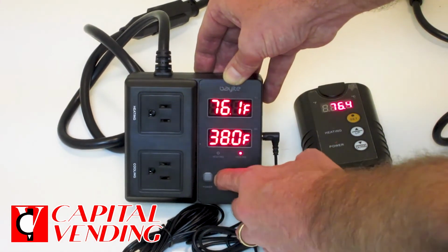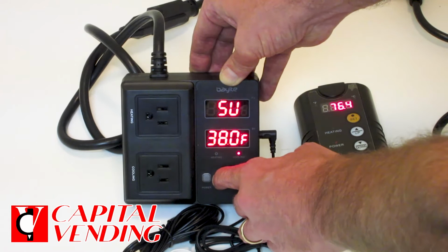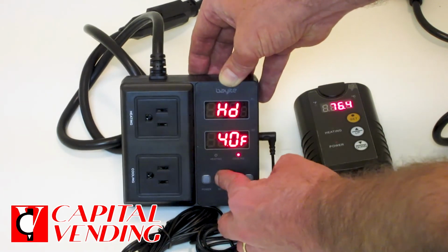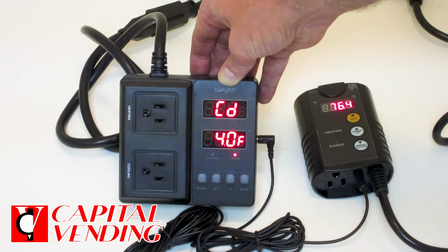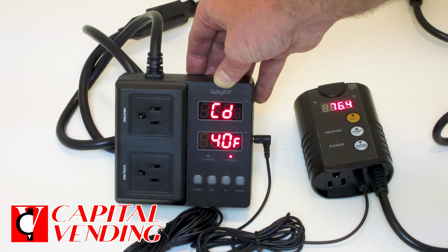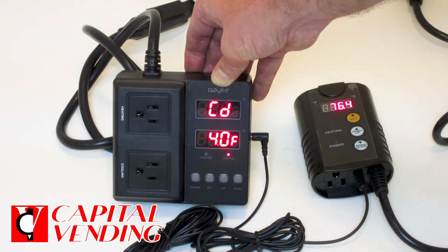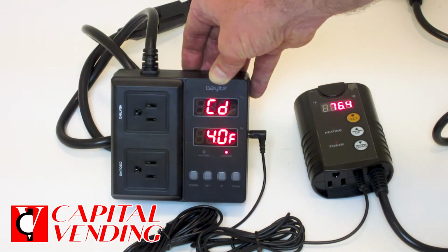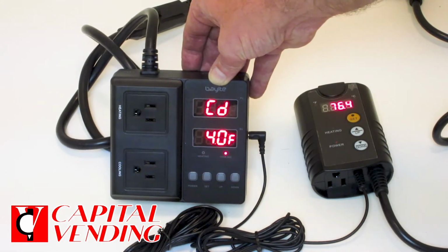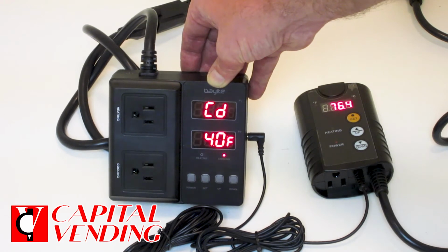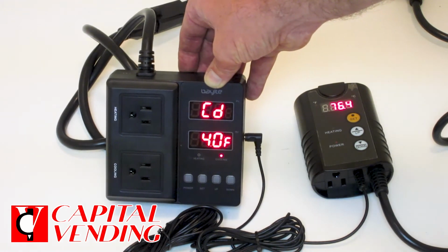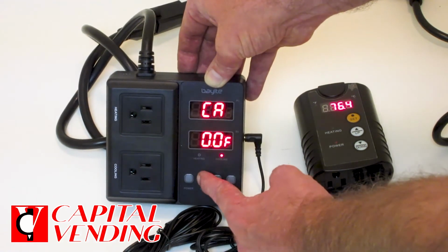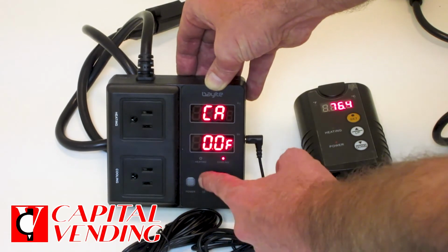So now I'm going to press and hold my set button again for 3 seconds. I'm here past my heating. Here's my cooling differential. Again, when you receive it, it'll be 4 degrees. So basically at 38 degrees, this is going to come on when it gets 4 degrees above that. So it's going to come on at 42 degrees, and it's going to keep the compressor running until you get to 38.